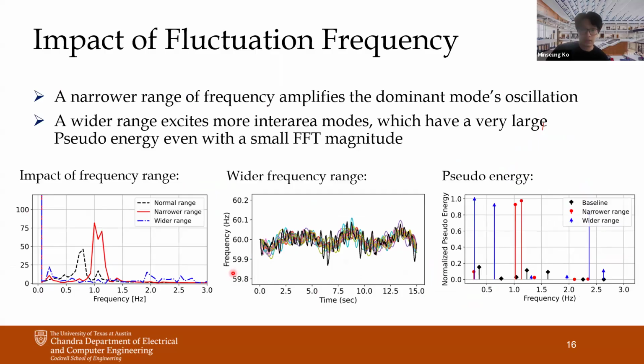This page shows the impact of the fluctuation frequency range, which I discussed in modeling the data center. We tested from a narrow range of fluctuation frequency to a wider range. Of course, the narrow range generally leads to higher excitation of the local mode around 1 Hertz, so you can see that the narrow range leads to a larger FFT magnitude in the local mode oscillations. But in the case of the wider range, you can see noticeable FFT magnitude at the lower frequency level, which is at the inter-area modes.